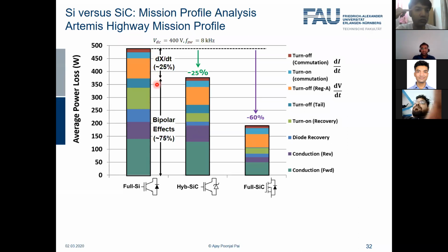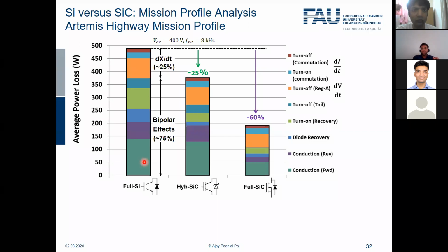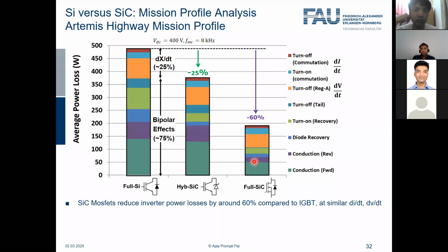So if you see here, 75% of the total losses come mainly from bipolar effects like tail current and recovery, and only 25% come from switching faster or slower. Even if you switch the IGBT really fast, you can only influence that 25% — the rest stays more or less the same. In fact, switching faster actually increases reverse recovery. So even switching an IGBT very fast, you can't influence that big 75%. For that, we need to go from a bipolar device to a unipolar device — that's the message.